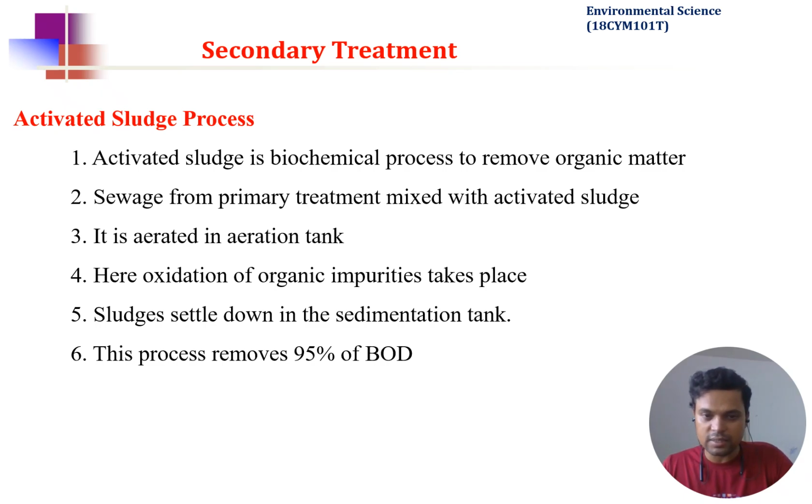Sludge settles down in the sedimentation tank, which I showed earlier, and this process can remove up to 95% of the BOD, which is very effective. You can increase the retention time in the aeration tank, and the removal could be increased a little bit, but after a certain limit it cannot go further, because there are some compounds, like nitrogen-containing compounds, which cannot be digested that easily or quickly by the bacteria. That would take up to 20 days, which is too long. We cannot wait that many days for a single treatment process.